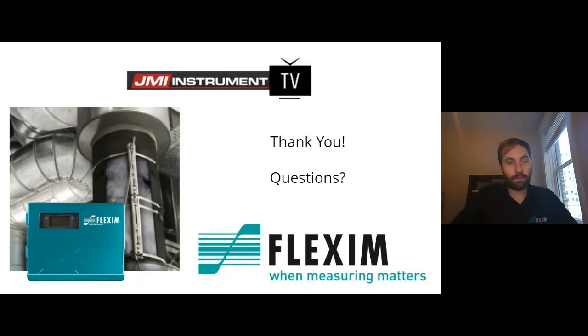Well, with gas measurement, which is transit time, the same as liquid measurement, when we start seeing a second phase of medium, so if we start seeing liquid and gas, we have a couple of diagnostics that are indicators of a second phase called variable amplitude and variable time. Variable time can also be blow by, or if the velocity is being exceeded. But it's a really good indicator, along with signal noise ratio, SNR.